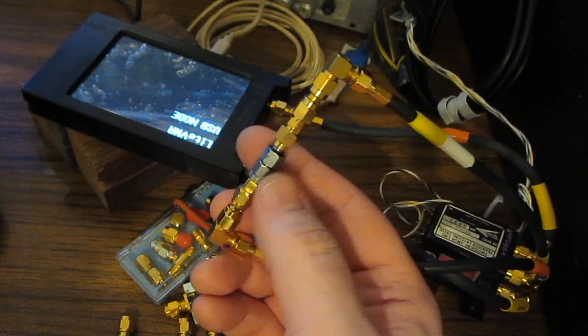So now I have our 10 dB Midwest microwave attenuator. I'll attach that to our transfer relay. Now we'll select transmission rectangular, and you can see we're reading basically between 10.2 and, I'd say, maybe 9.9. It's very flat. This particular attenuator is good all the way up to 18 gigahertz that they specify it for.